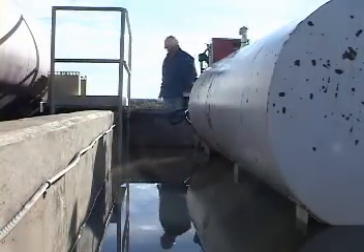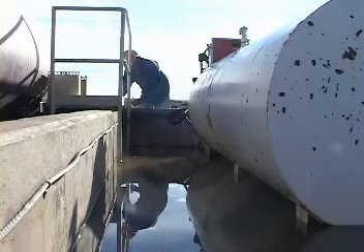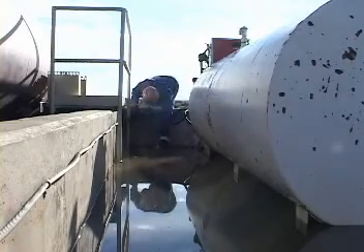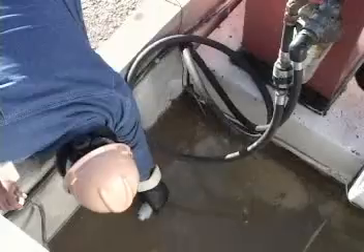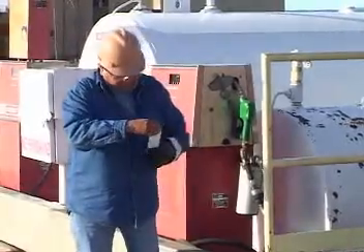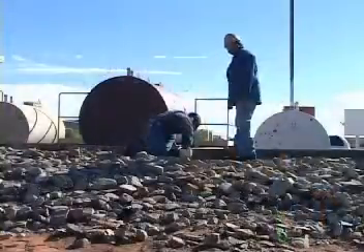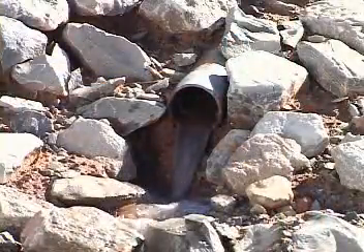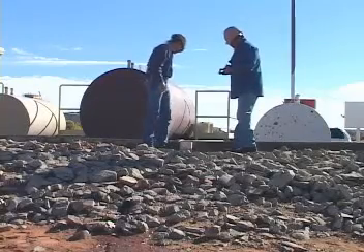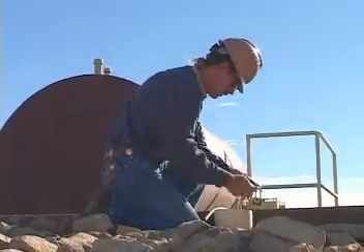If water must be drained, such as when the equipment needs servicing or the water level becomes too high, the accumulated rainwater must be clean and free of contamination. If the tank has leaked or overflowed, the rainwater may have been contaminated and cannot be discharged into the environment. A supervisor or other designated person must determine that the rainwater is clean before okaying the discharge. He or she will also make a record of the event for filing with the stormwater plan. After draining, the drain valve must again be locked in the closed position.